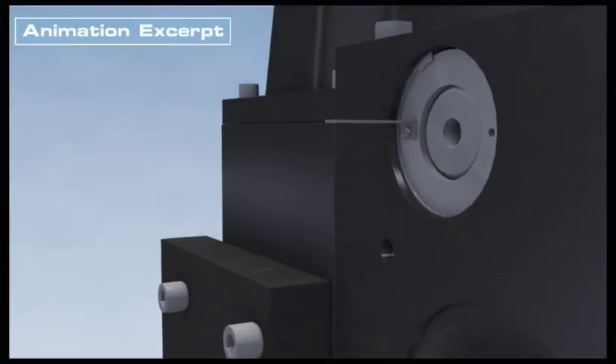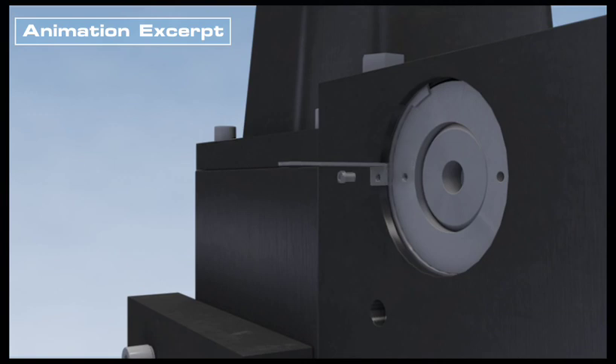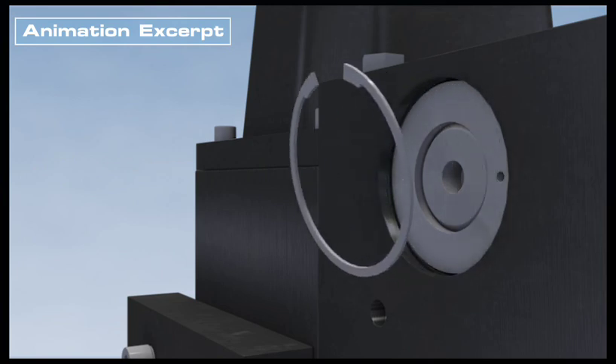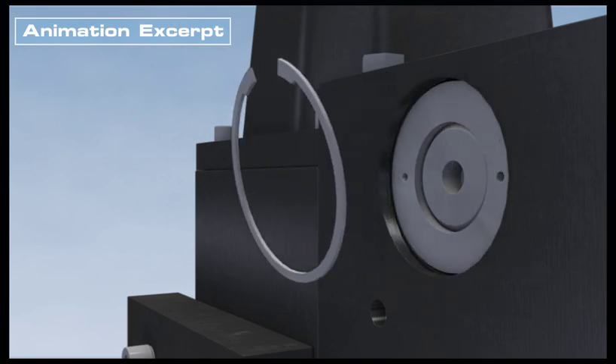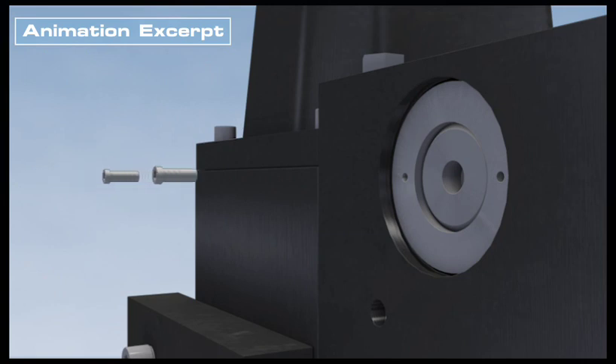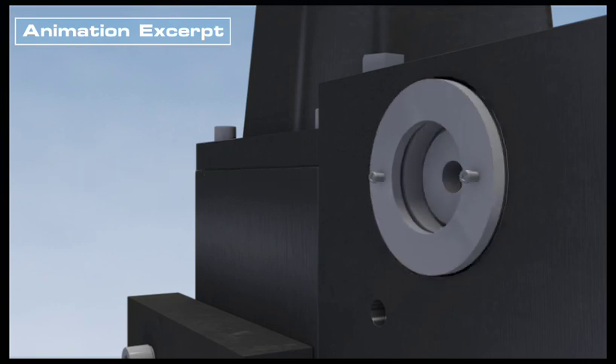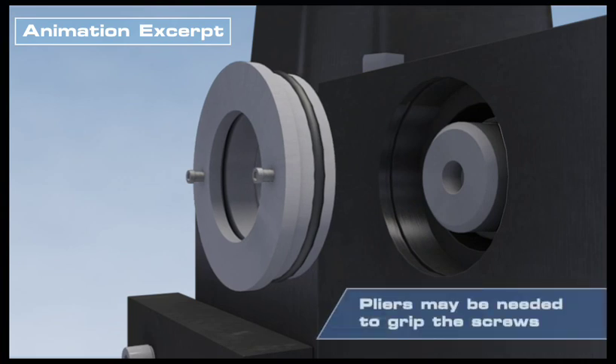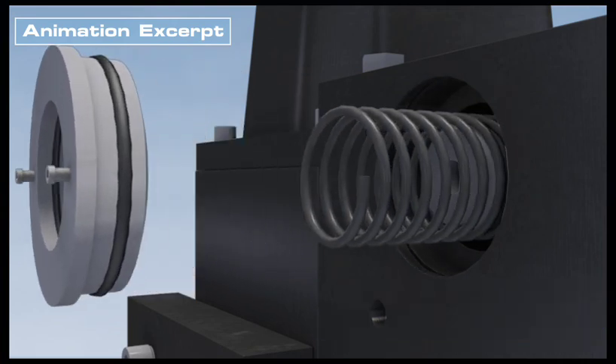To disassemble the oil reservoir, remove the level scale, followed by the retaining ring. Insert two 6/32 screws onto the reservoir cover and pull it out. Remove the spring.